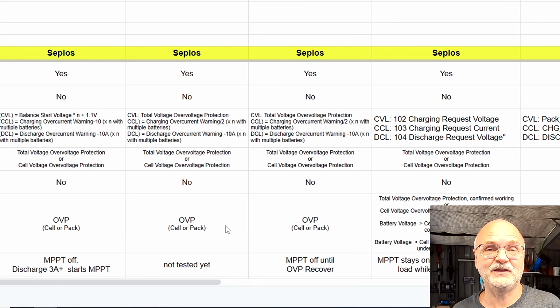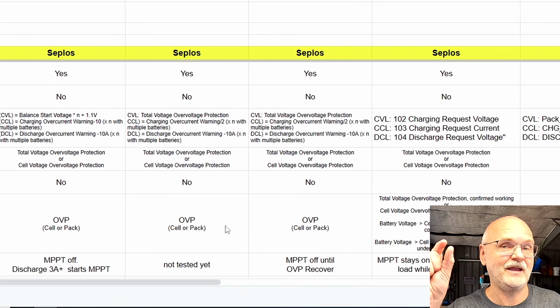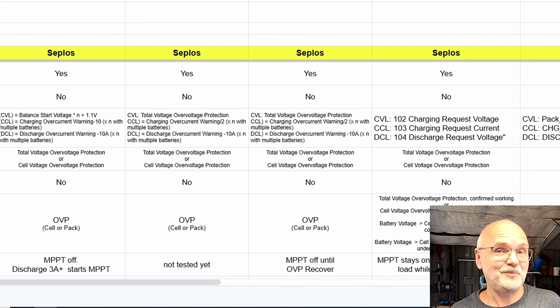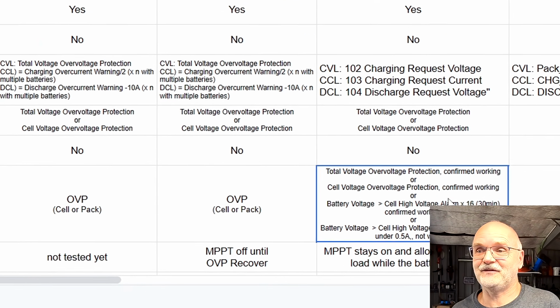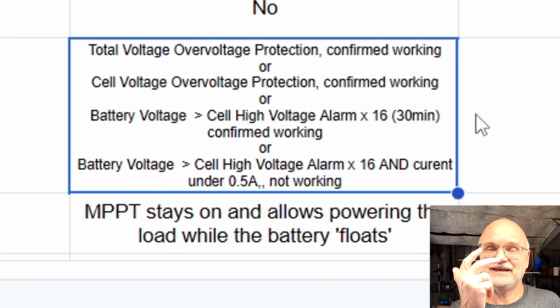They always needed this protection status to just reset to 100%. And clearly, if one cell hits 3.65 volts, this doesn't mean the battery is on 100%. This is only one cell that is on 100%, but not the other ones. And I've complained about this since day one with SEPLOS, and maybe because of that they finally have changed it.